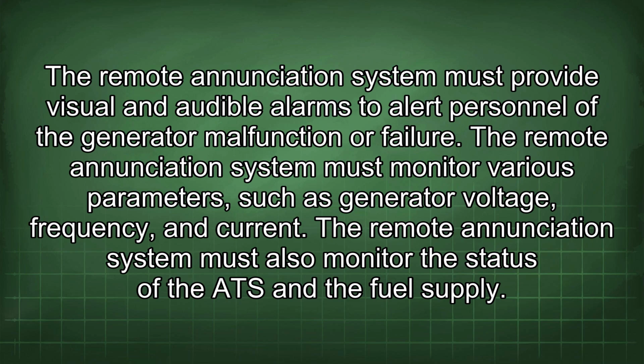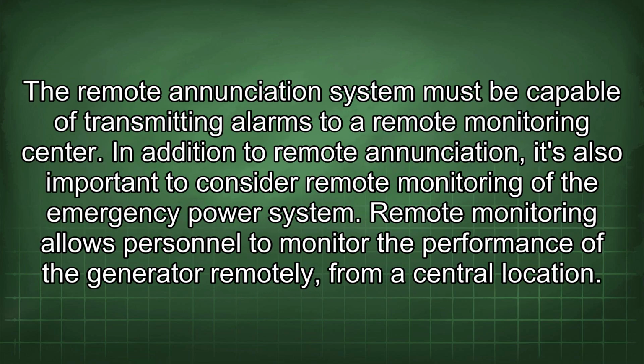failure. The remote annunciation system must monitor various parameters such as generator voltage, frequency, and current. The remote annunciation system must also monitor the status of the ATS and the fuel supply. The remote annunciation system must be capable of transmitting alarms to a remote monitoring center.